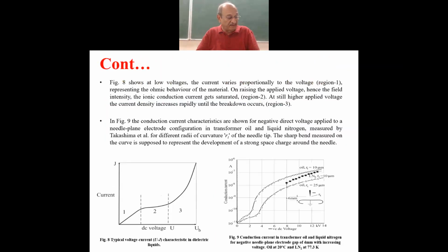In the last lecture I talked about the pre-breakdown phenomenon in solid and liquid dielectrics. The currents through the solid dielectrics before the breakdown are slightly higher in magnitude. You can imagine solid dielectrics have the epsilon r, the relative permittivity, higher, unlike the gases we have talked about. So the capacitance formed by the solid and liquid dielectrics is higher, and you can imagine there will be more current through the dielectric when epsilon r is higher.